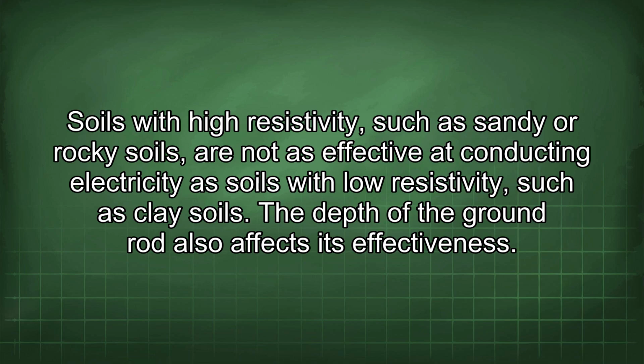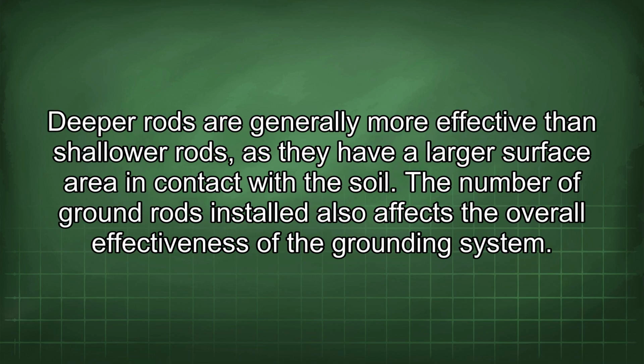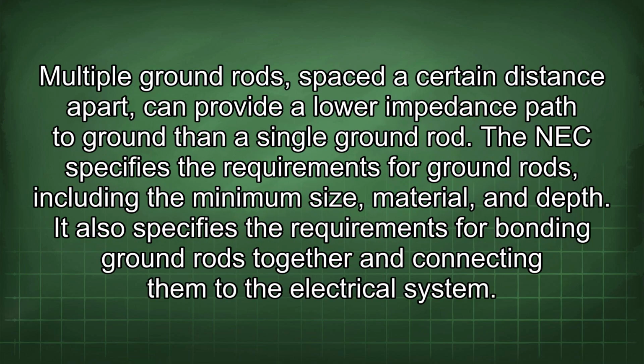The depth of the ground rod also affects its effectiveness. Deeper rods are generally more effective than shallow rods, as they have a larger surface area in contact with the soil. The number of ground rods installed also affects the overall effectiveness of the grounding system. Multiple ground rods, spaced a certain distance apart, can provide a lower impedance path to ground than a single ground rod. The NEC specifies the requirements for ground rods, including the minimum size, material, and depth.